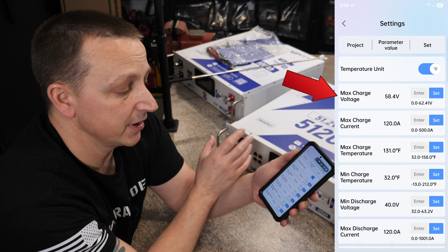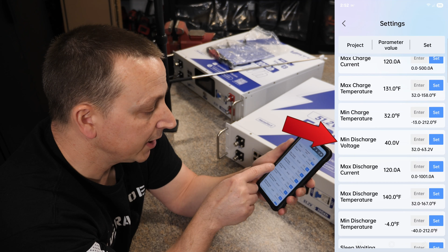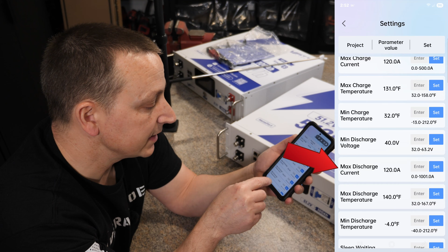Max charge voltage is 58.4, that's basically full charge, so we probably don't want to change that. Max charge current is set at 120. There are some temperature ranges in there too. Minimum discharge voltage is 40, and max discharge current is 120. So basically 120 up and 120 down.